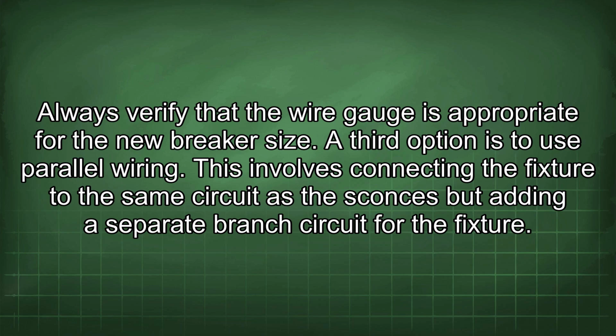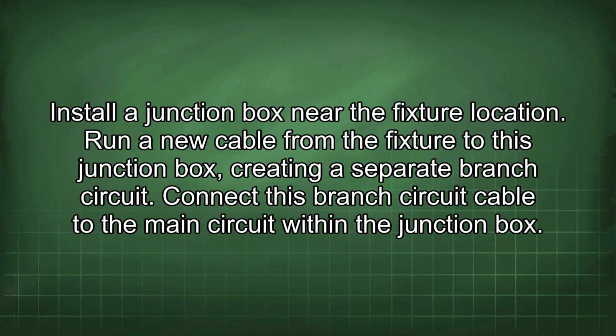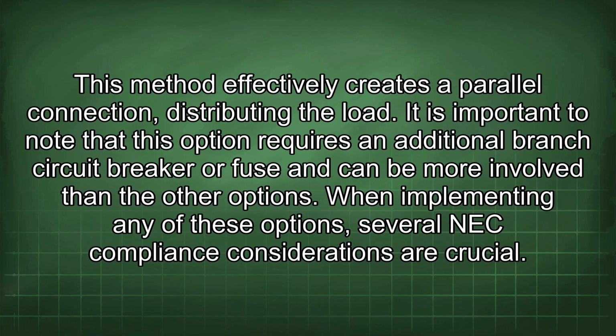A third option is to use parallel wiring. This involves connecting the fixture to the same circuit as the sconces but adding a separate branch circuit for the fixture. Install a junction box near the fixture location. Run a new cable from the fixture to this junction box, creating a separate branch circuit. Connect this branch circuit cable to the main circuit within the junction box. This method effectively creates a parallel connection, distributing the load. It is important to note that this option requires an additional branch circuit breaker or fuse and can be more involved than the other options.